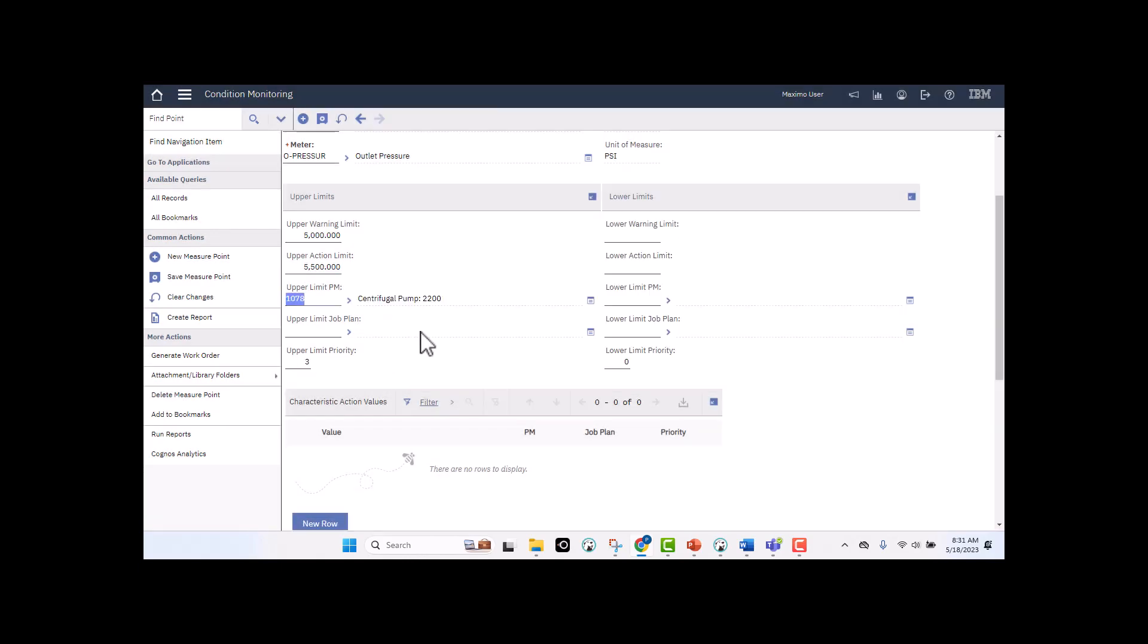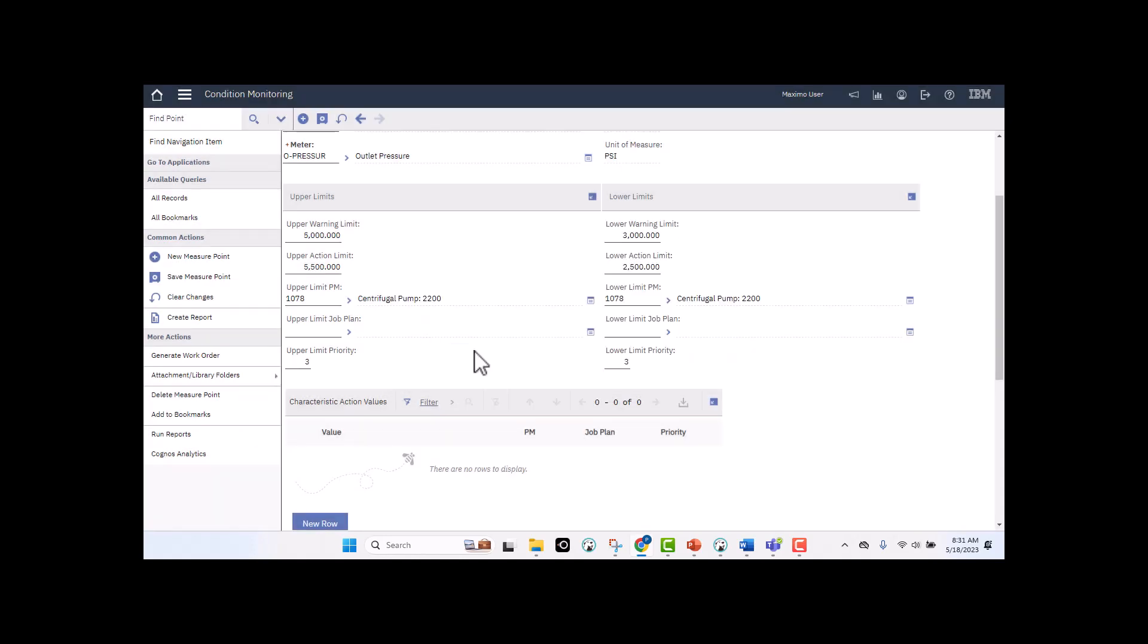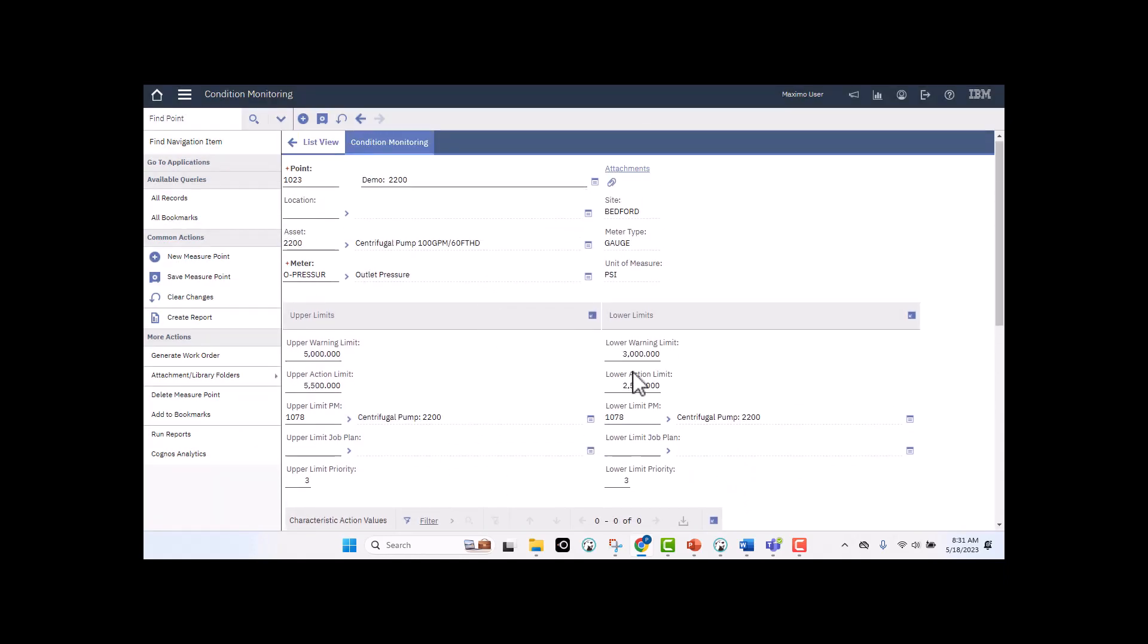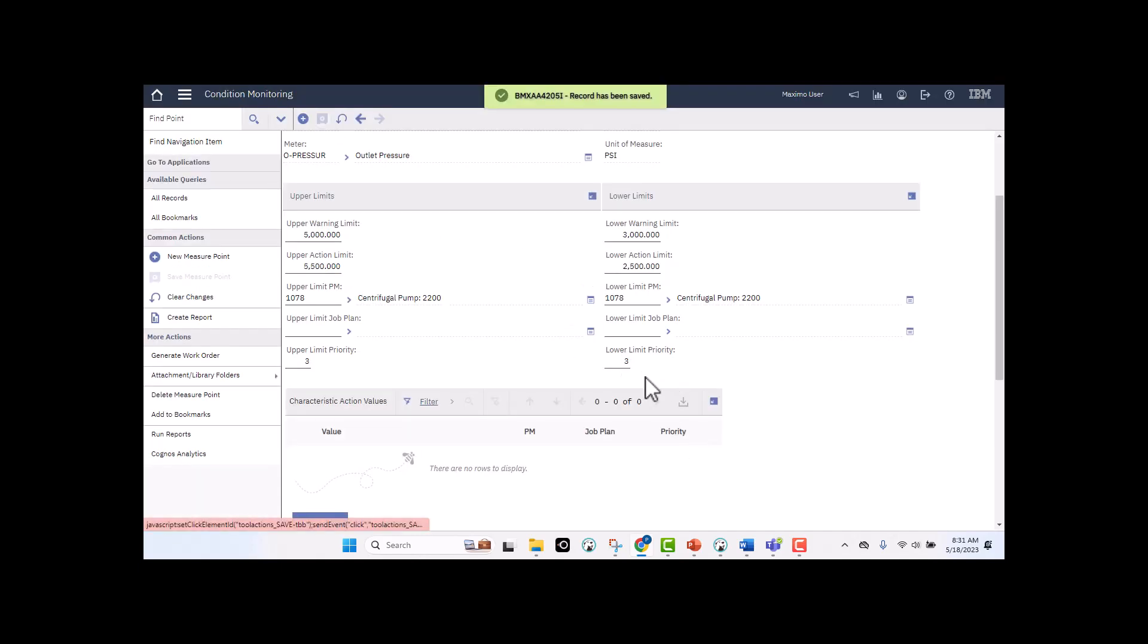So in my case, I'm going to select the PM that's associated with that asset. So I'm going to generate a PM work order, and I have a default priority here of 3. So that's perfect. So again, these are the upper limits. For my lower limits on my pressure reading, I'm now going to set this at 3000. Again, that's the yellow line. If it goes below that, let's say 2500, this again is where I need to take an action. I'm going to select that same PM value, that is associated with my asset 2200, and Maximo built that relationship for me. And again, it's going to create it with a lower limit priority for my work order of 3.